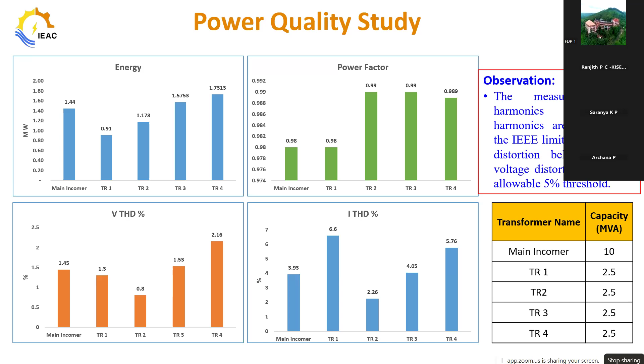You can do energy analysis to check the quality of your supply. We do part load analysis normally for 24 hours, starting the power analyzer at a set time and running it for 24 hours. After that, it automatically switches off and all the data is plotted and stored in the power quality analyzer, giving us load analysis, load factor calculation, and supply quality.